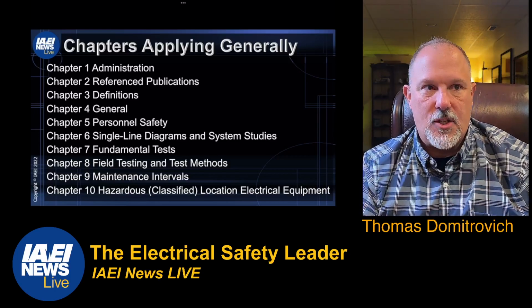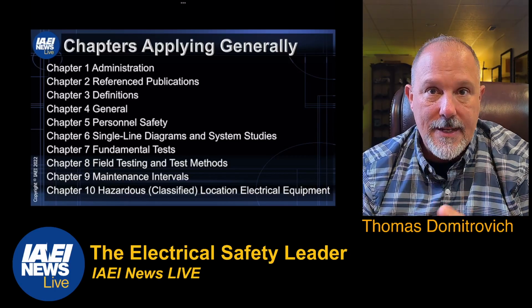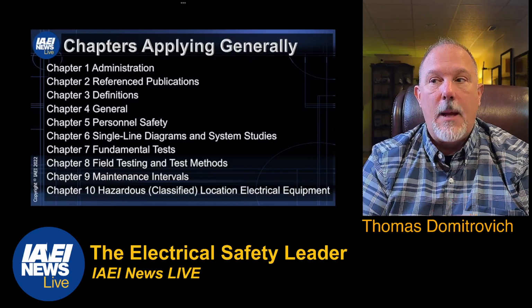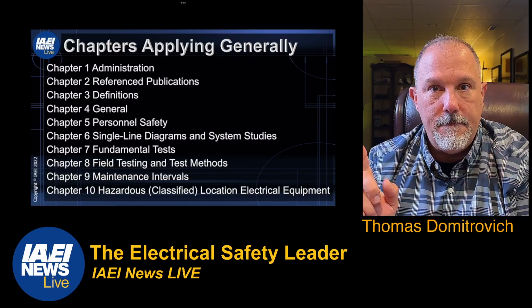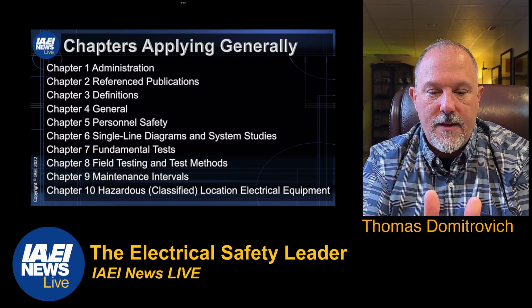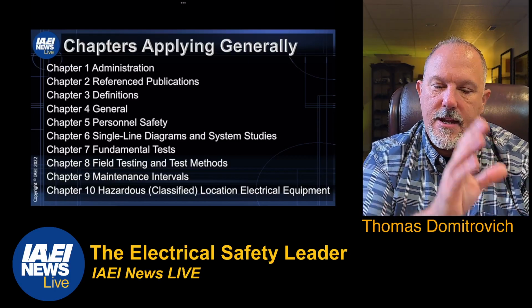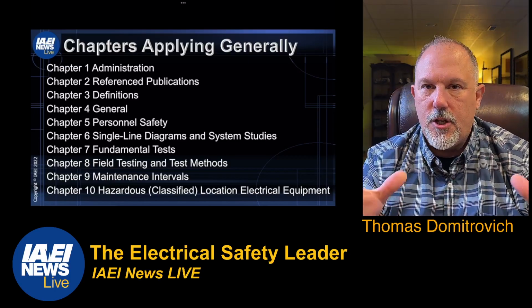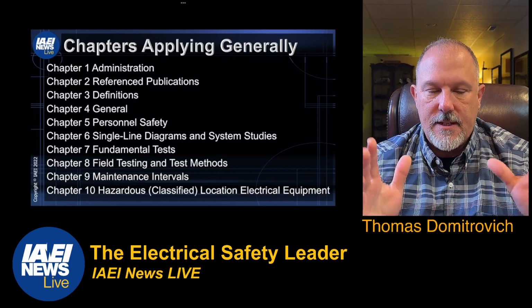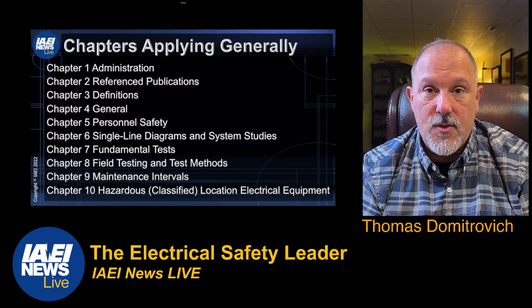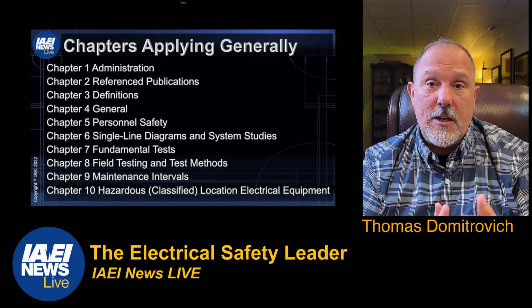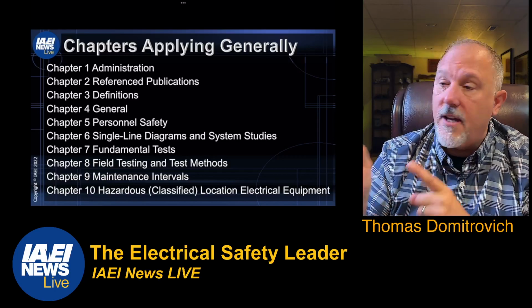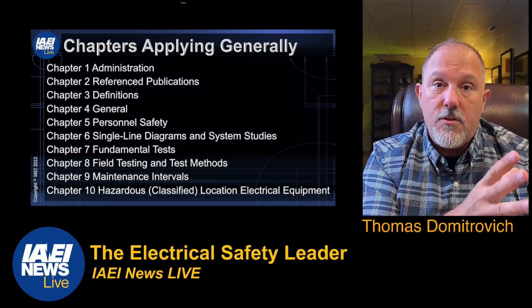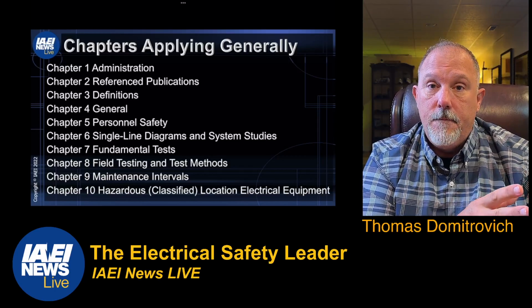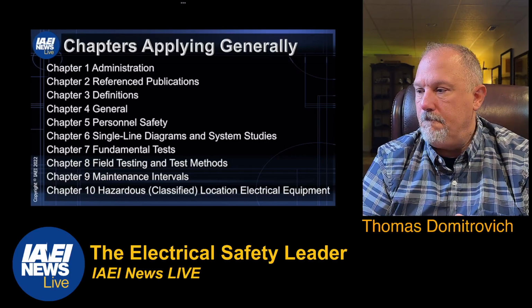Any document out there that talks about maintenance—it's okay to just say it shall be maintained, and point to 70B. You can have NFPA 99, the National Electrical Code, all these other codes and standards that say you need to pull maintenance, and if there's anything special for that piece of equipment not covered in 70B, give me those special criteria—but point to 70B.